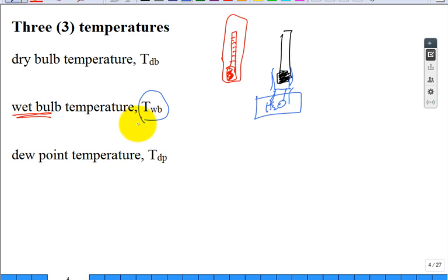My wrist is making it go in a circle, slinging it around. Now, what I sling around has two thermometers on it. One, the sensing element is just exposed to the air that it's flowing through. The other has a little sock. It's connected to a reservoir on the end with a little bit of water, and I don't want to spill it out if there's any dripping out right there. So one thermometer stays wetted and the other is the dry bulb temperature.